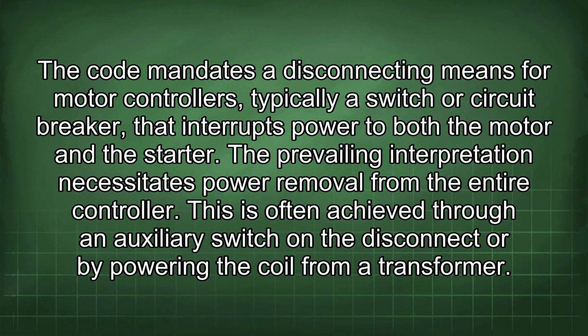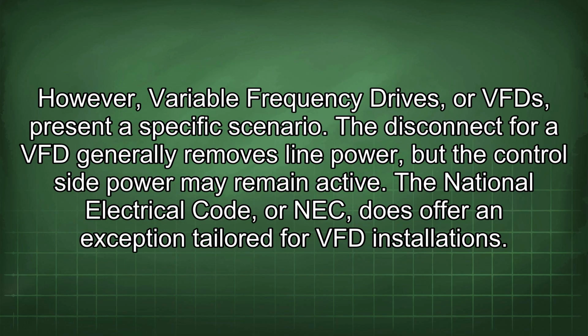Code mandates a disconnecting means for motor controllers, typically a switch or circuit breaker that interrupts power to both the motor and the starter. The prevailing interpretation necessitates power removal from the entire controller. This is often achieved through an auxiliary switch on the disconnect or by powering the coil from a transformer. However, variable frequency drives, or VFDs, present a specific scenario. The disconnect for a VFD generally removes line power, but the control side power may remain active.